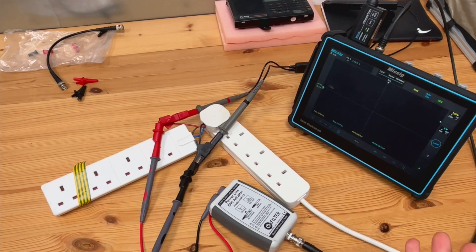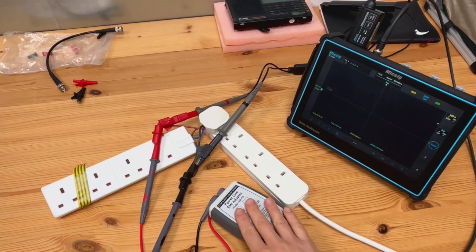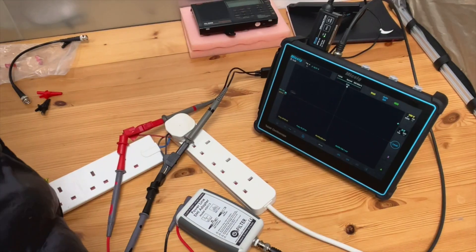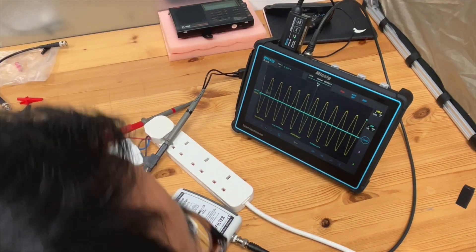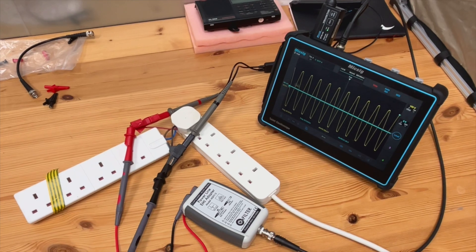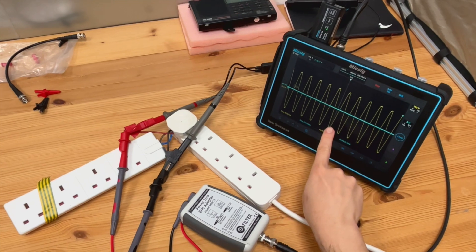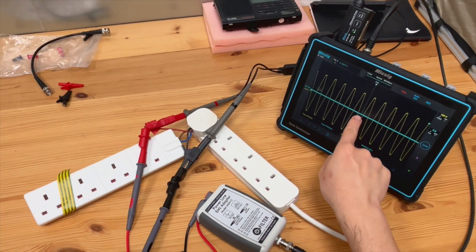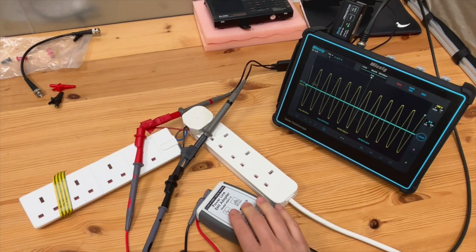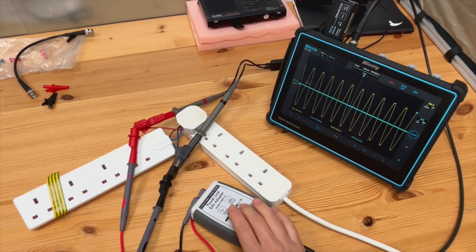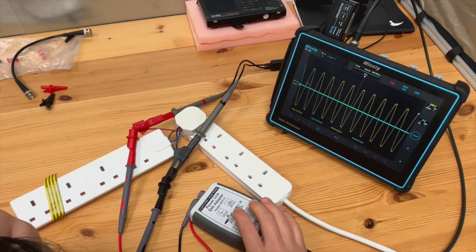You're going to see whether this transient event would be captured by this adapter. Let's do that. Yeah, I just switched on the lights in the room and there's an associated transient event there and it's captured by this module because it's on channel two and it's not captured on channel one. Clearly this one has much better performance in terms of capturing this transient event compared with your normal differential probe.